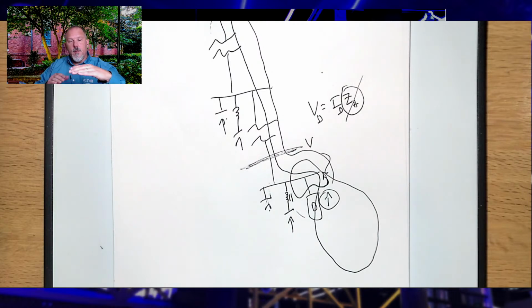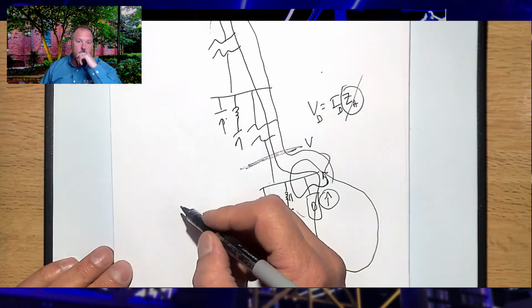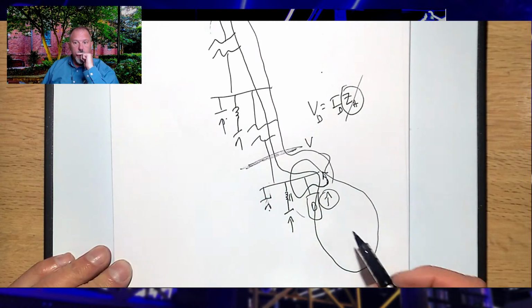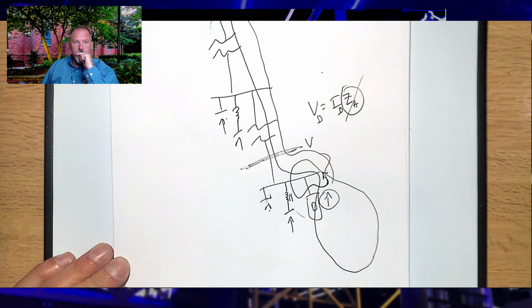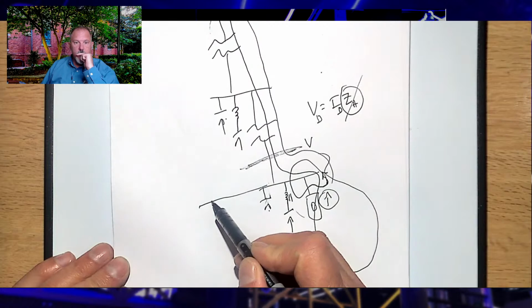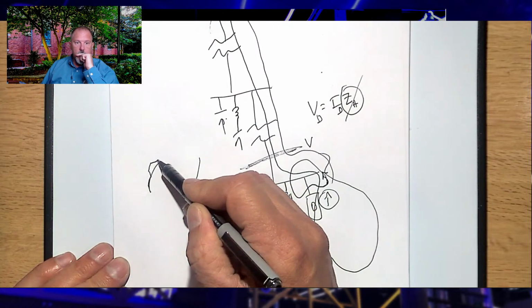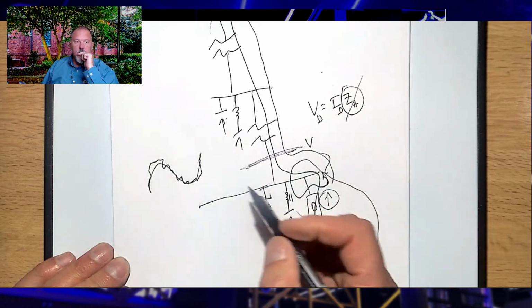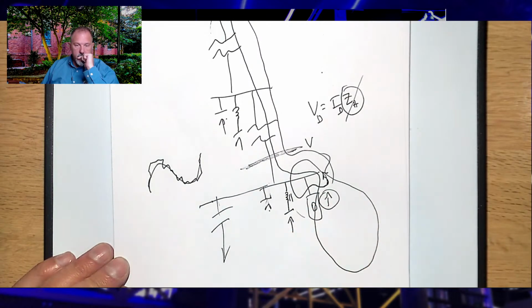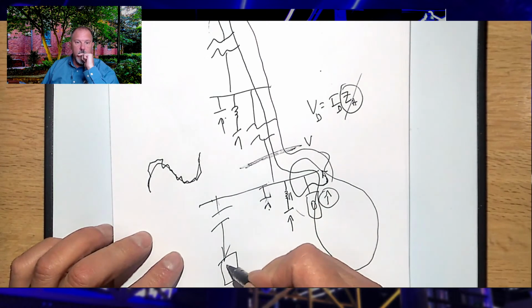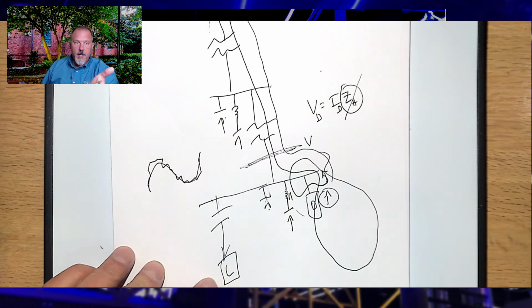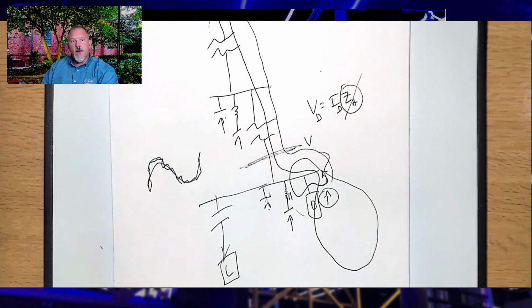Right, and the importance of the voltage distortion is that if you distort the voltage, now you're impacting a wider area in the facility, from the power distribution system. So harmonics are a two-part problem. One is current distortion, pushing current up through the system and causing heating. The other, like you said, is if I screw up my voltage, if my voltage is supposed to be nice and clean but I have flat topping or something bad, then everything on my system takes that voltage and uses it, on my other loads. Even if it was a linear load, linear being resistive, my current is going to look just like my voltage because it reflects voltage. A misoperation usually occurs with voltage distortion, where heating usually occurs with current distortion.